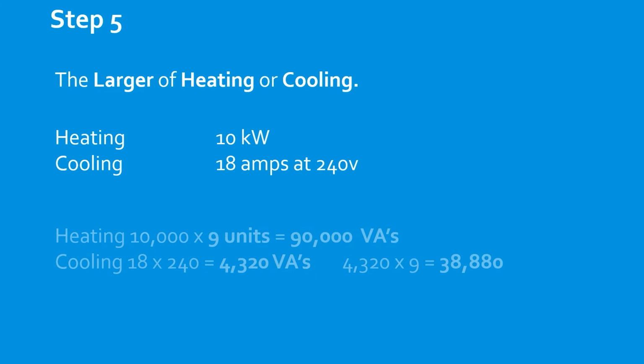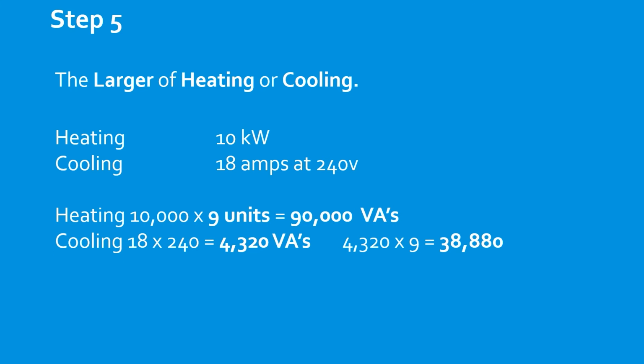Now let's select the larger of the heating or cooling. Each unit has a 10 kW heat strip and cooling at 18 amps at 240 volts. So we do 10,000 multiplied by 9 units equals 90,000 VAs, and the cooling is significantly less. So we end up, after applying Ohm's law, with 4,320 VAs per unit. You multiply that by 9, and you're only going to get 38,880. So we're going to select the heating.